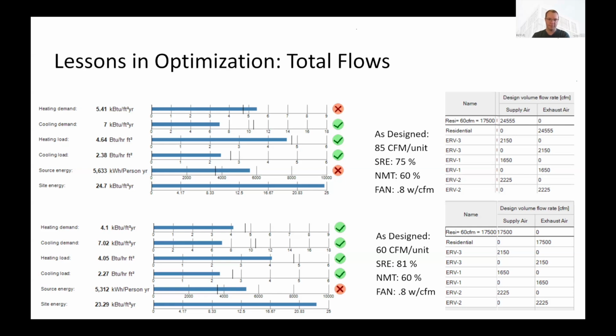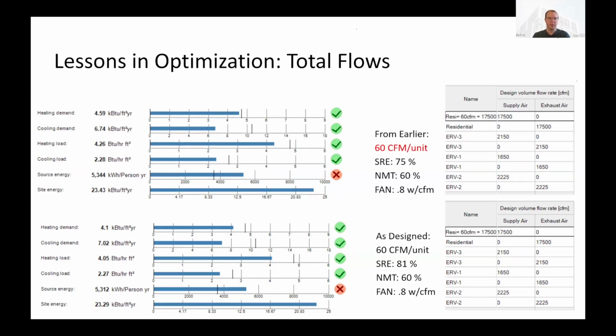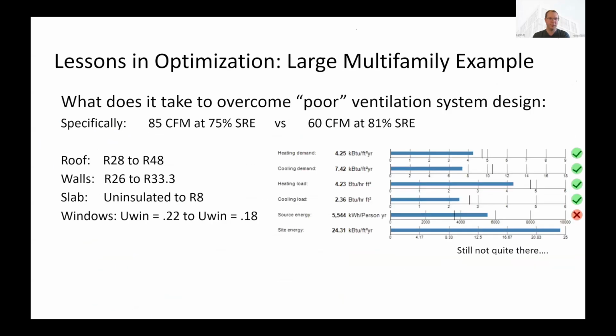And to keep this simple, I left fan energy and moisture transfer the same. But it's worth noting that these two things are combined. Less airflow means less overall heating need, but also less airflow means higher sensible recovery efficiencies. So you're getting more heat transfer, less heat losses that way too. And if we push this a little bit more, just to again do that comparison between the 4.59 and the 4.1, we can push it even more.